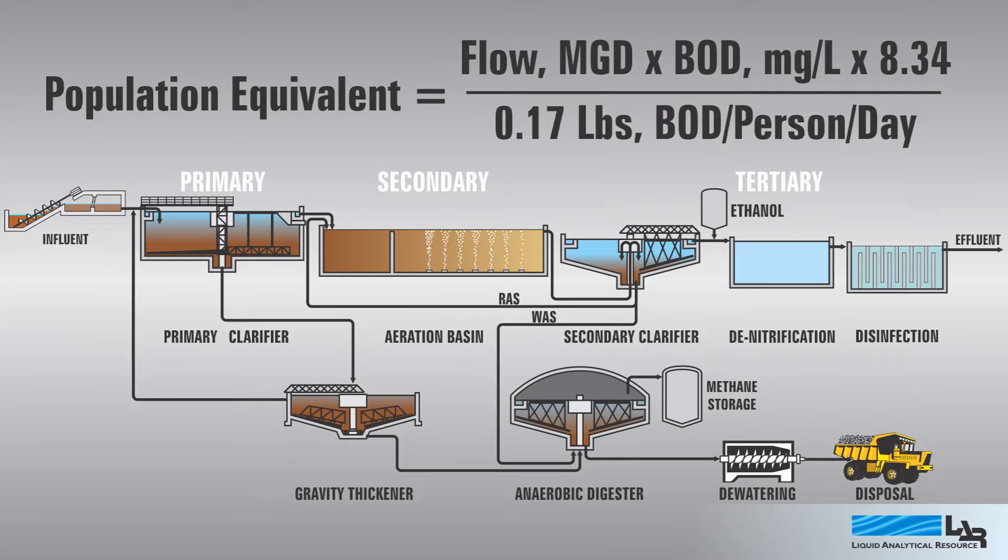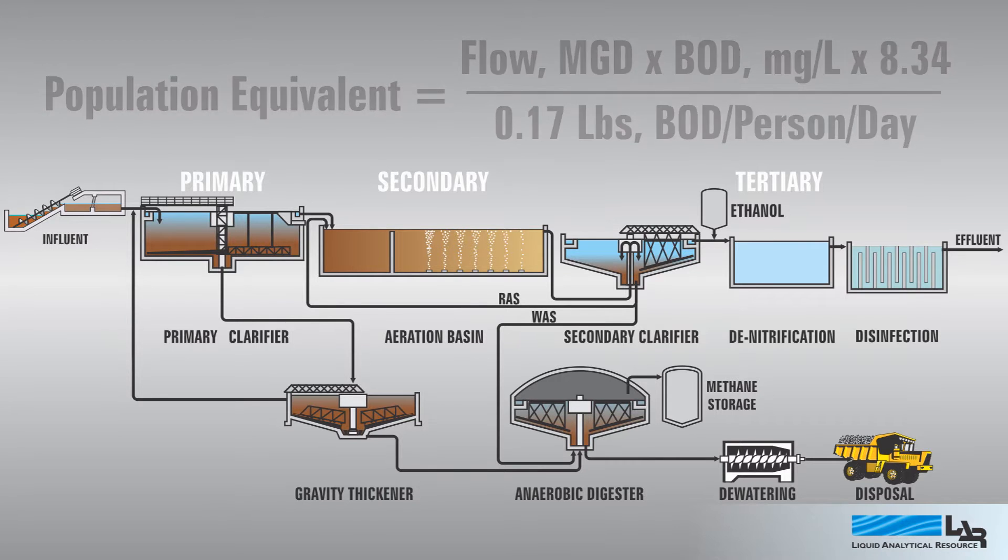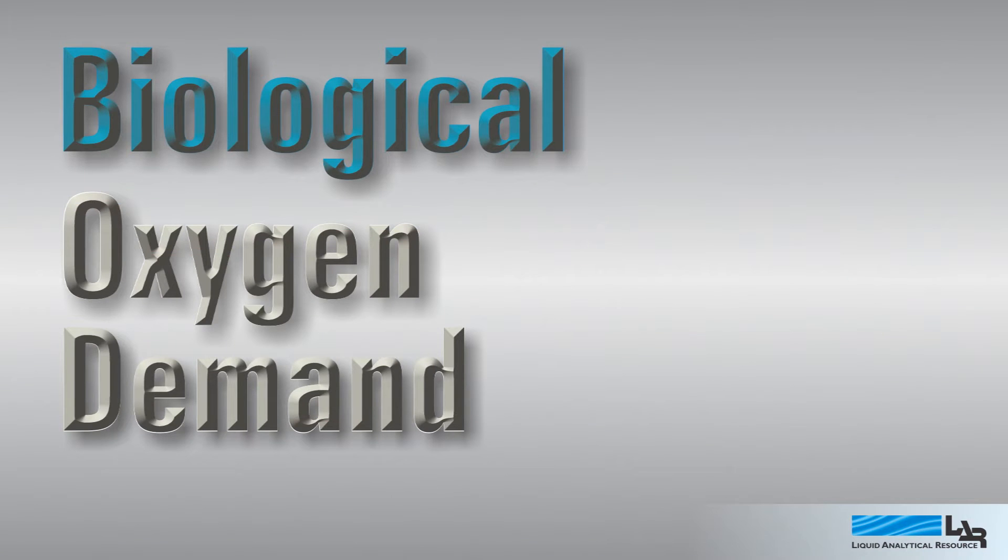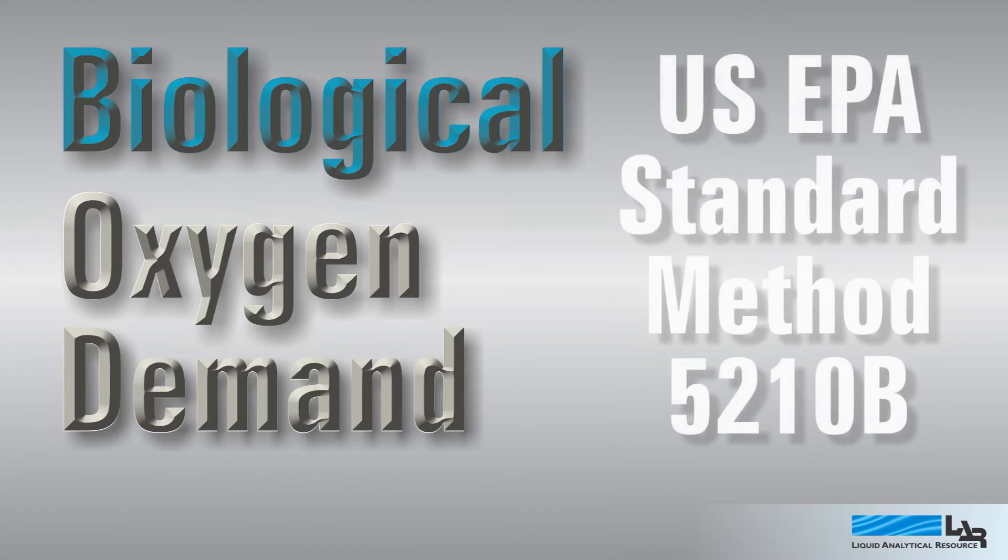Oxygen is so important to sludge treatment that a plant's capacity is defined in pounds per day of biological oxygen demand, or BOD. The standard method for measuring BOD is U.S. EPA Method 5210B. Since the test measures microbial oxygen consumption, it requires five days to complete.